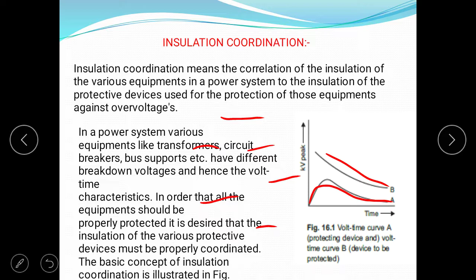Now the voltage time curve. The voltage time curve is a graph showing the relation between the crest flashover voltage and time to flashover for a series of impulse applications of a given wave shape. Waves of the same shape but of different peak values are applied to the insulation whose voltage time curve is required. If flashover occurs on the front of the waveform, the flashover point gives one point on the voltage time curve. The other possibility is that the flashover occurs just at the peak value of the wave, which gives another point on the curve.